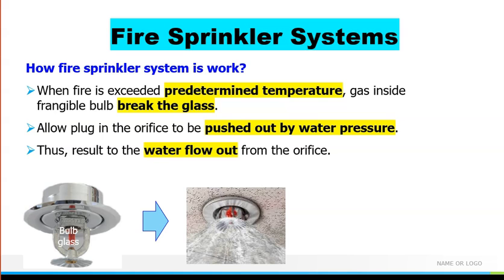And how does the fire sprinkler system work? Okay, when fire exceeds the predetermined temperature, the gas inside this bulb will break and allow the plug in the orifice to be pushed out by the pressure of the water. So the water will come out from the nozzle here, from the orifice.